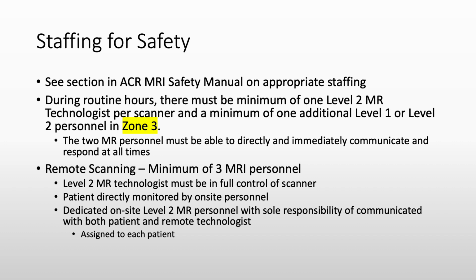There is also guidance on remote scanning, and this section will require a more detailed review of the ACR manual for those sites that intend to conduct remote scanning. In general, a Level 2 MRI technologist must be in full control of the scanner. The patient must be directly monitored by on-site personnel, and a Level 2 MRI personnel must be dedicated to the patient and remote technologist.